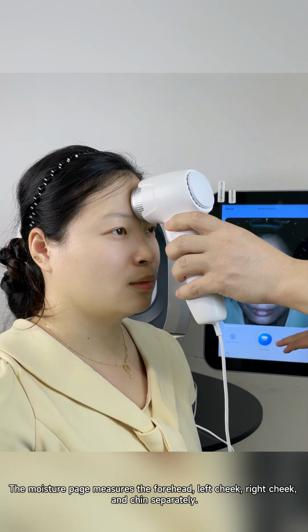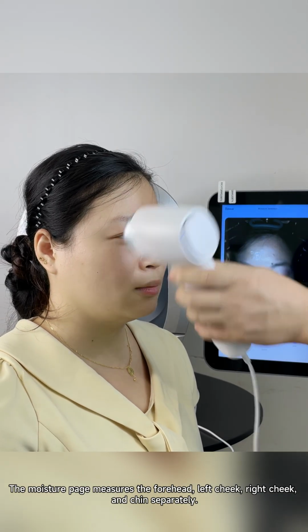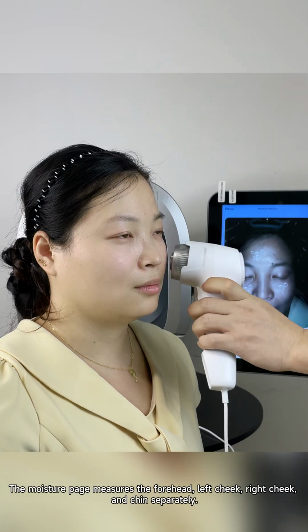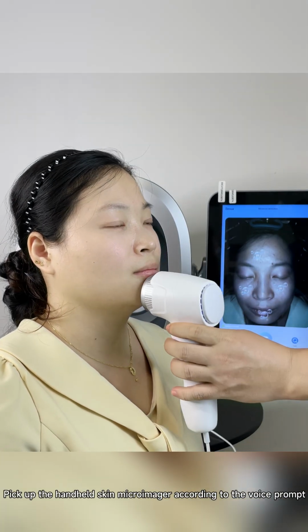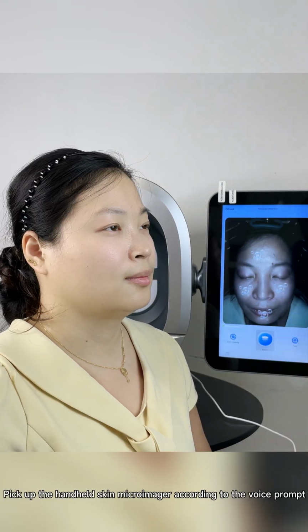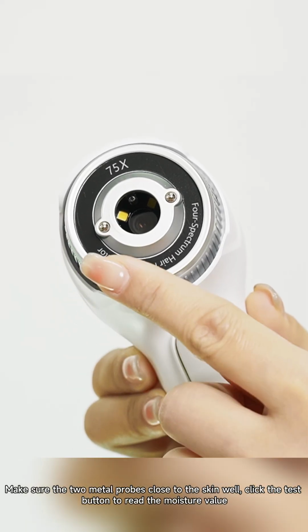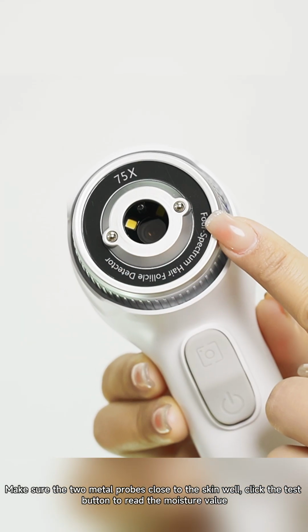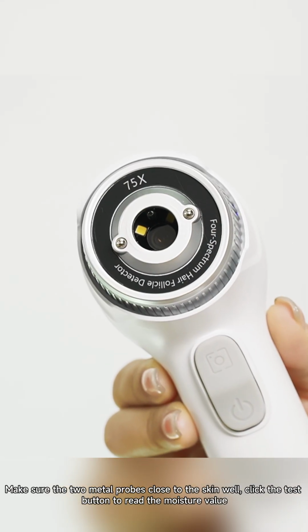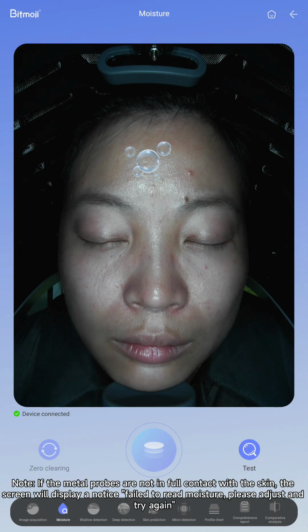Skin Moisture Content. The moisture page measures the forehead, left cheek, right cheek, and chin separately. Pick up the handheld skin microimager according to the voice prompt. Make sure the 2 metal probes are in close contact with the skin. Click the Test button to read the moisture value. Note, if the metal probes are not in full contact with the skin, the screen will display a notice: failed to read moisture. Please adjust and try again.